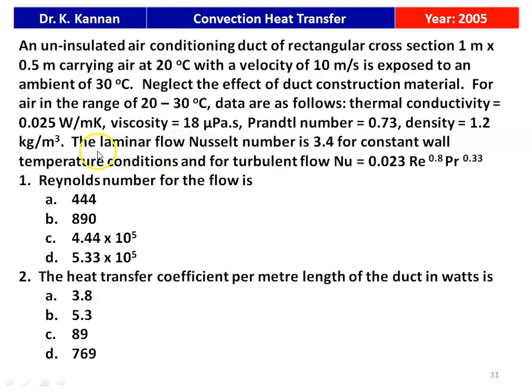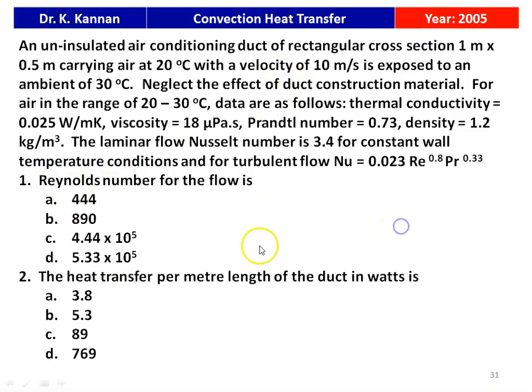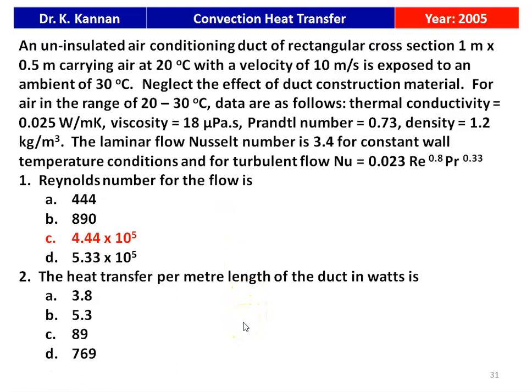The laminar flow Nusselt number is 3.4 for constant wall temperature condition, and for turbulent flow, Nusselt number equals 0.023 × Re^0.8 × Pr^0.33. For this problem there are two questions: first, calculate the Reynolds number for the flow; second, calculate the heat transfer per meter length of the duct. The answer for the first question is Re = 4.44 × 10^5, and for the second question, heat transfer per meter length is 769 watts.